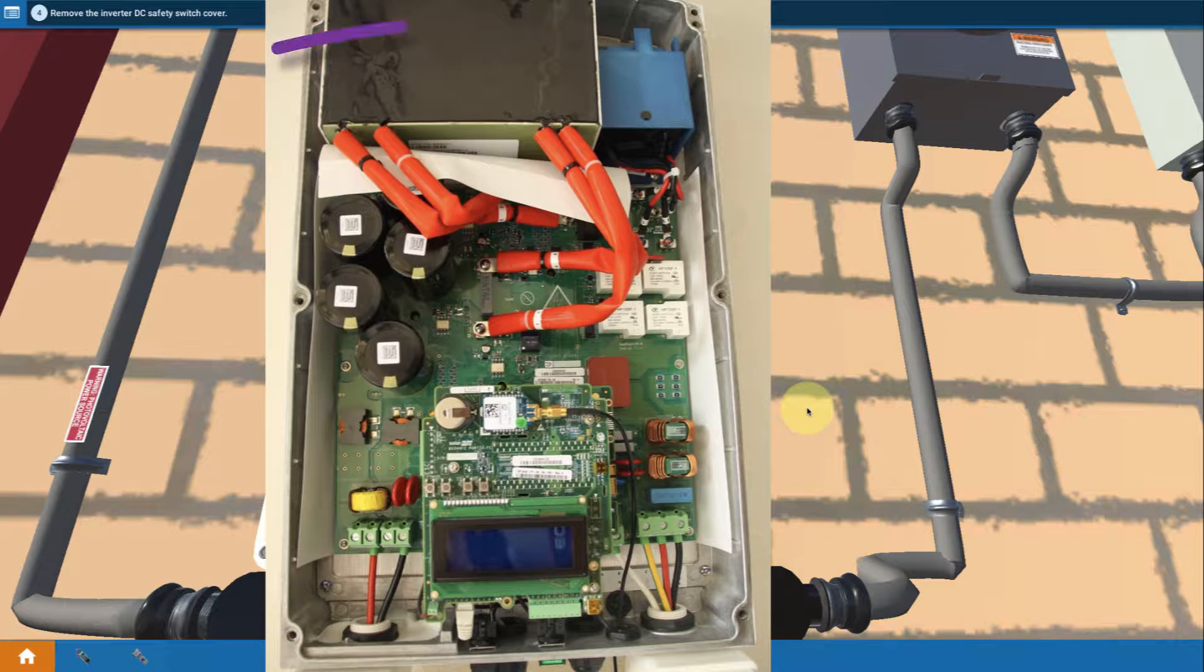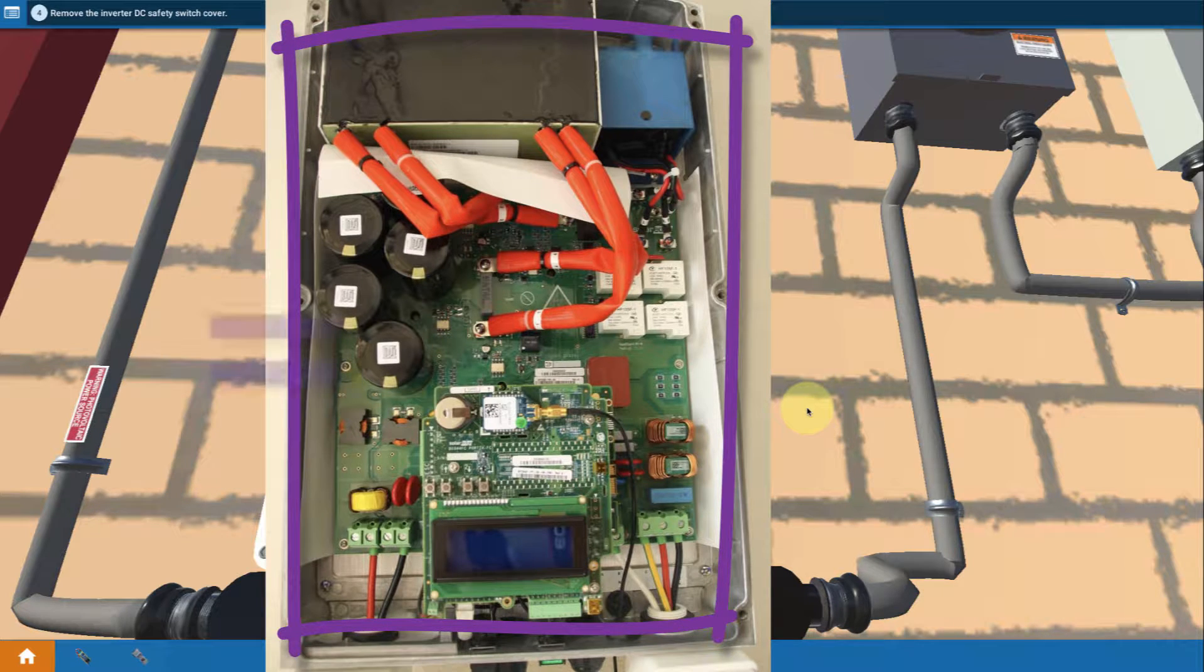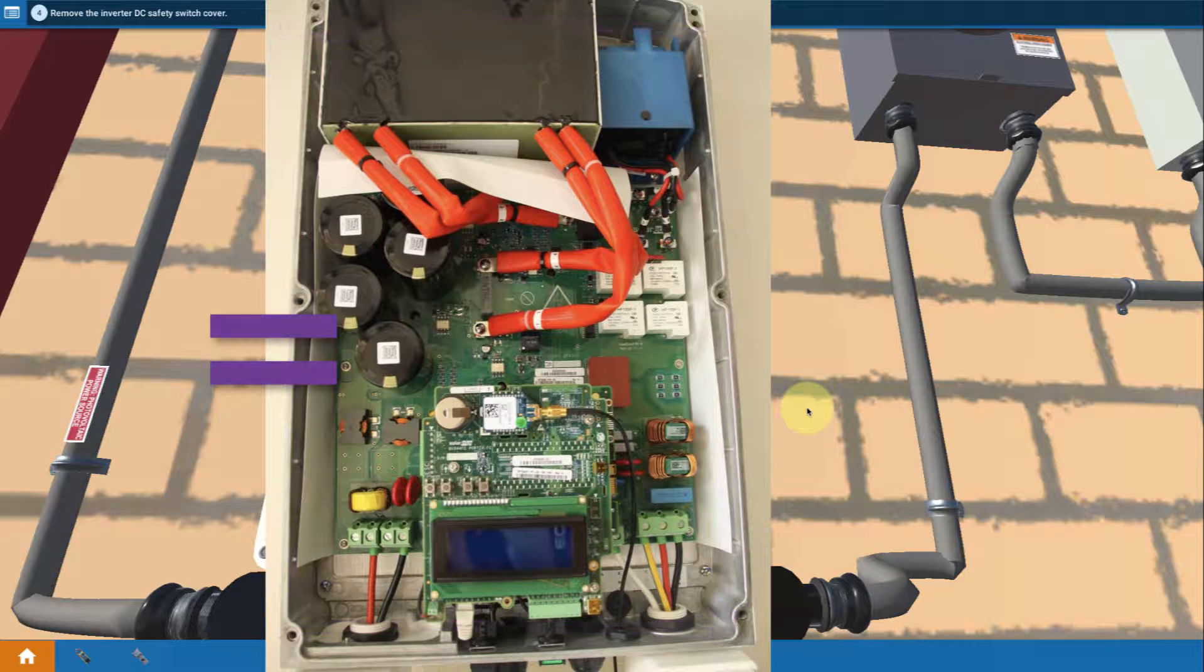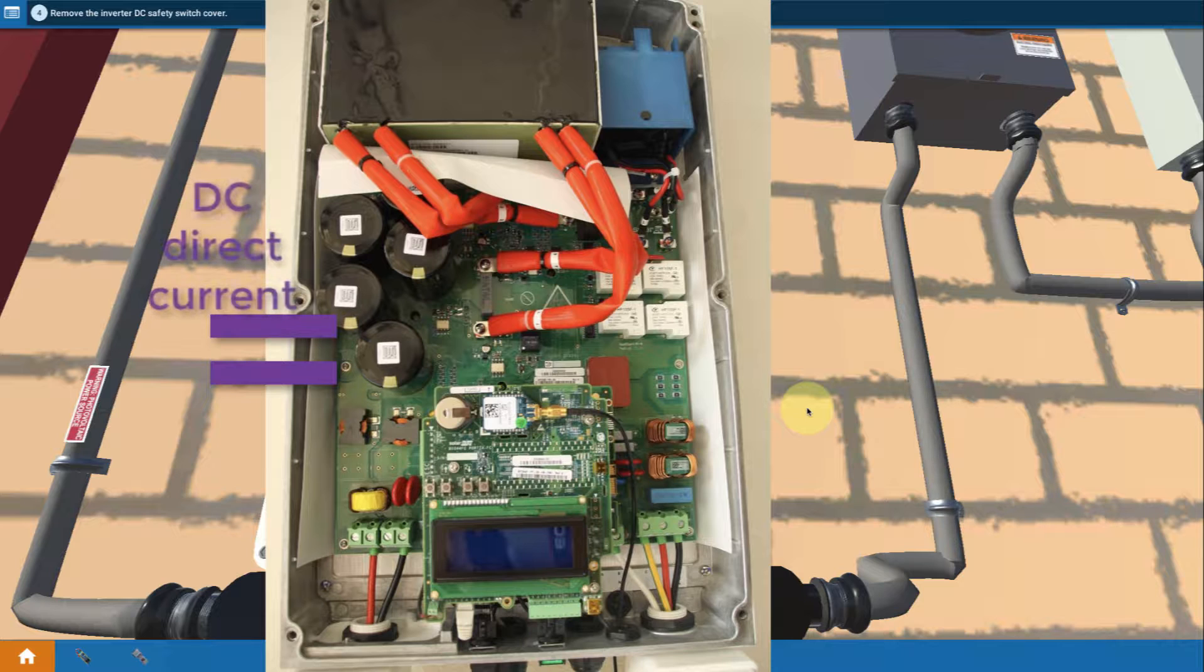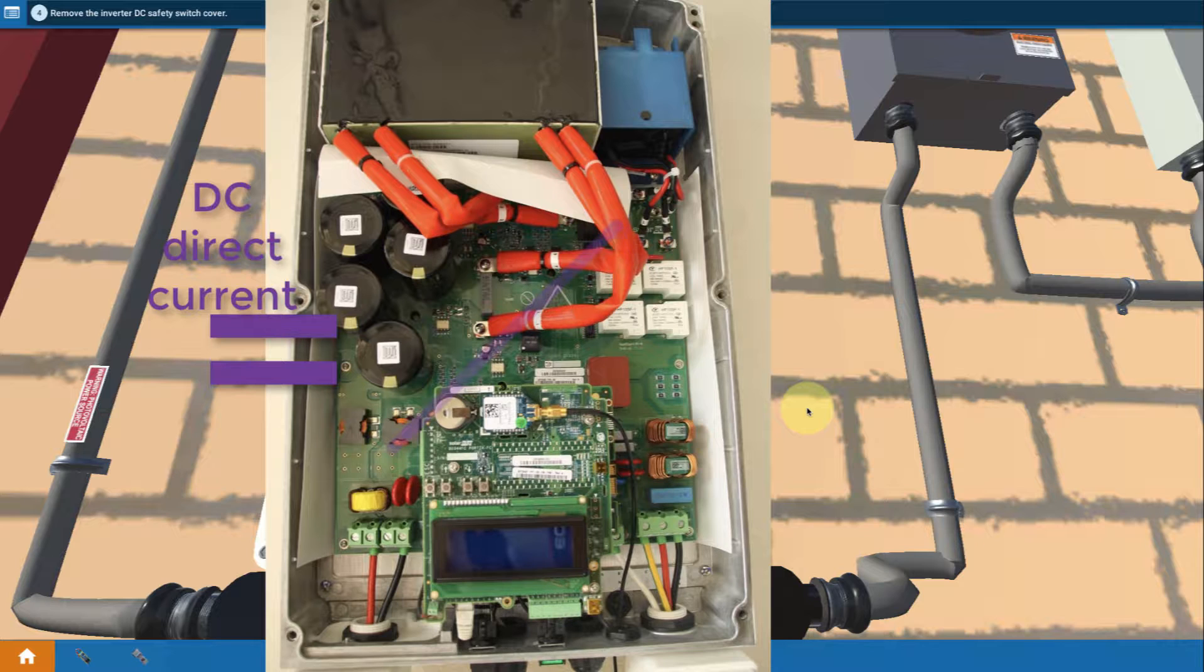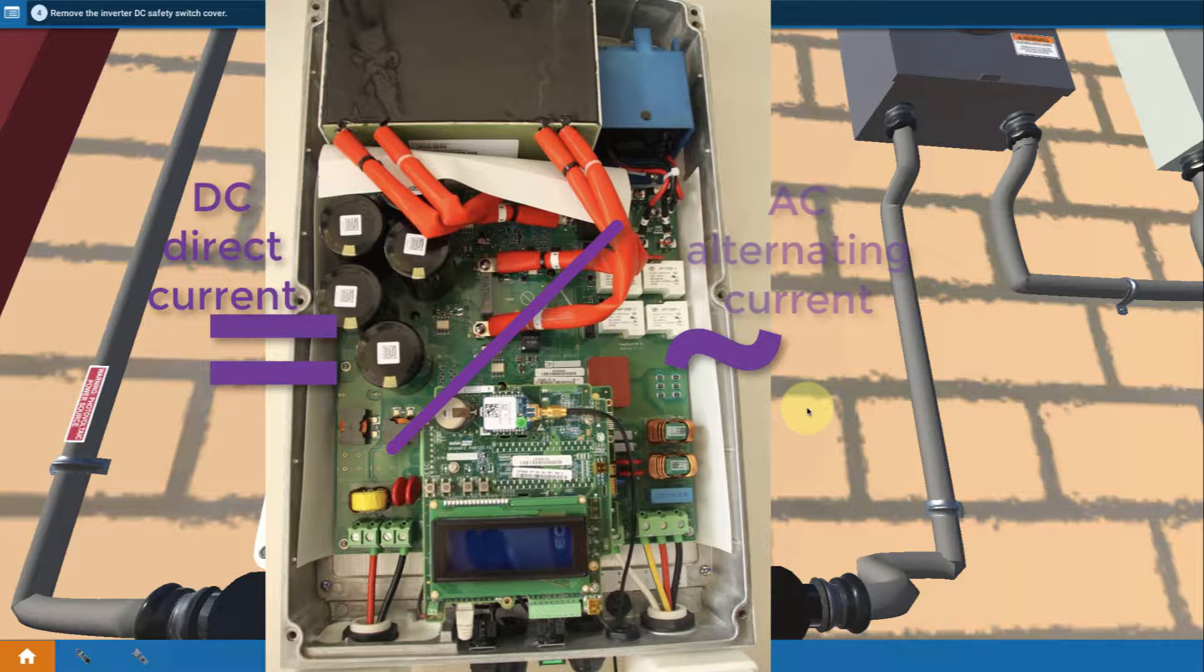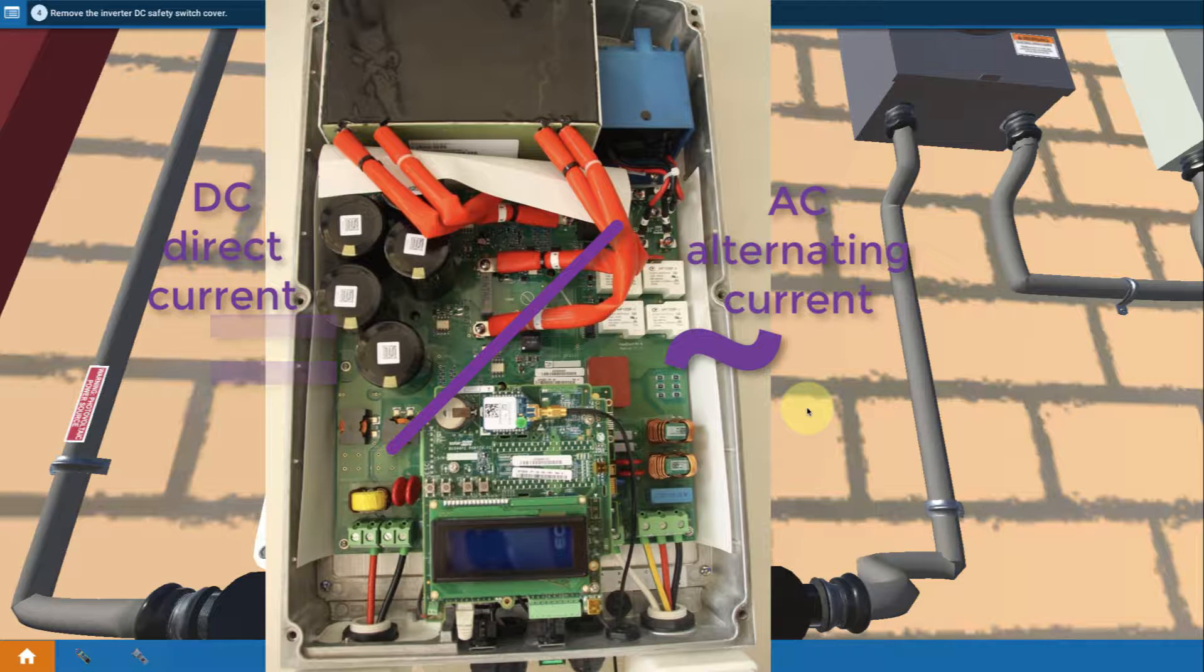But the idea is that in here is where the DC or direct current electricity from the solar panels, kind of like a battery, just straight voltage, is brought in and it's chopped, broken up, filtered, refined, synthesized back into a sine wave, alternating current sine wave at 60 cycles or 60 hertz, which is standard for the U.S., and 240 volts nominal output, which is standard for U.S. residential.